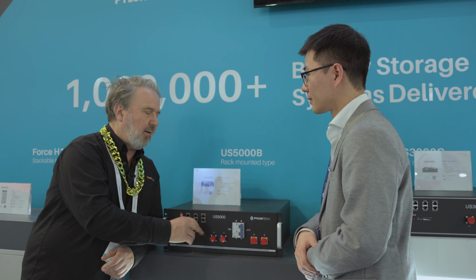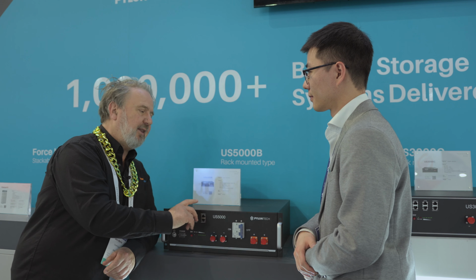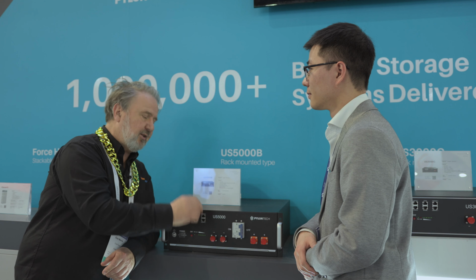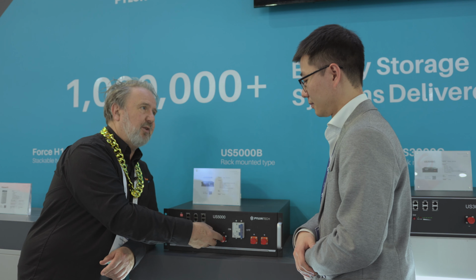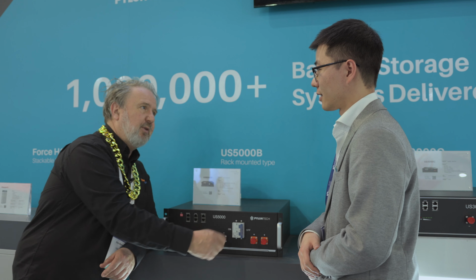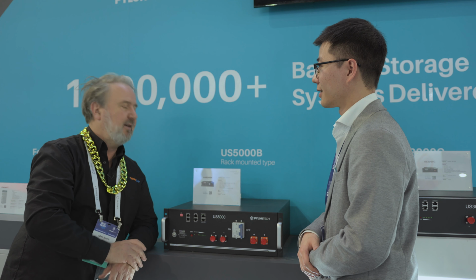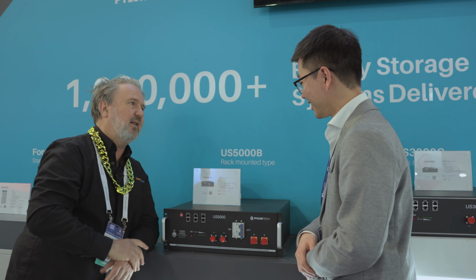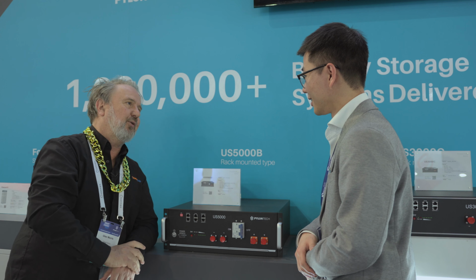Now, these are 48 volt nominal, connected in parallel with each of the units. So you've got in and out positive, in and out negative on the front here, with interconnecting cables. And hence that's the reason for the limit of 16 - that's the maximum current you can draw through that string.